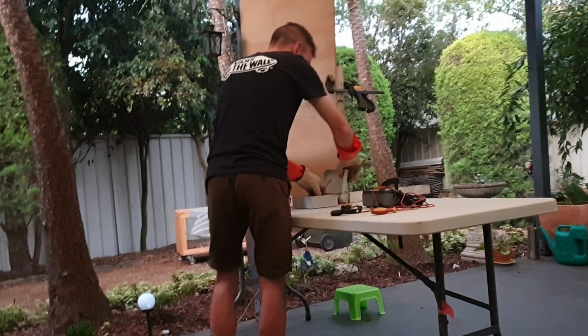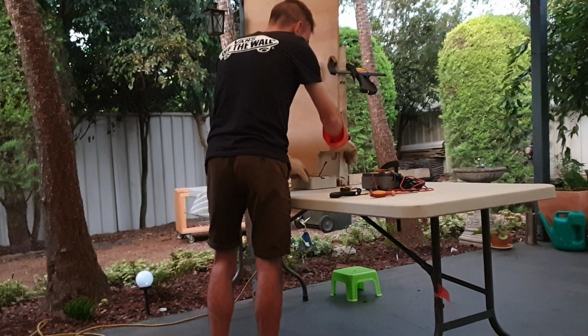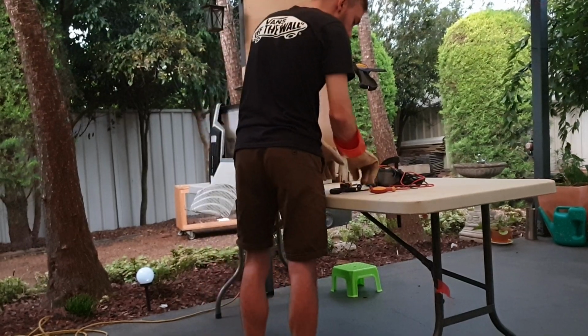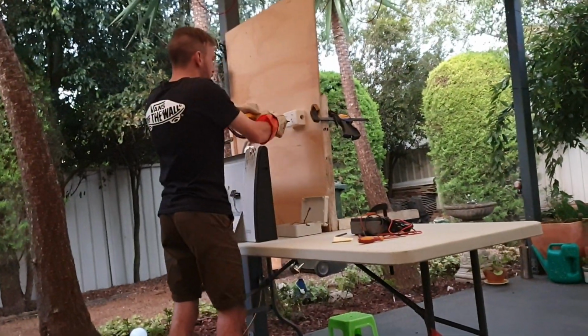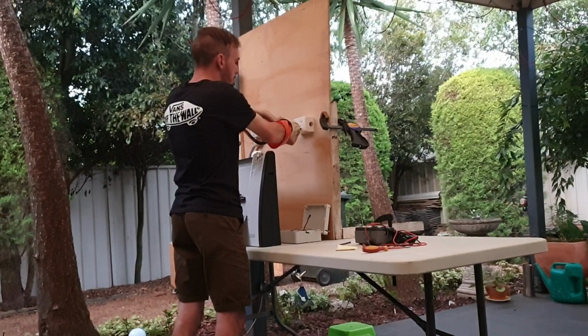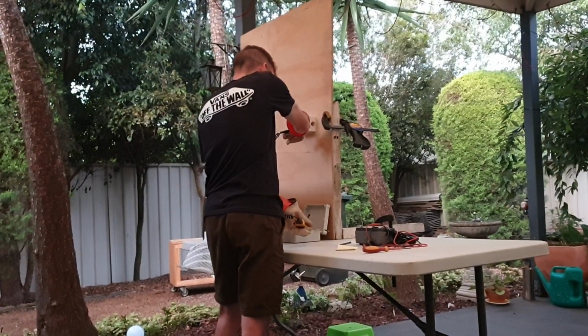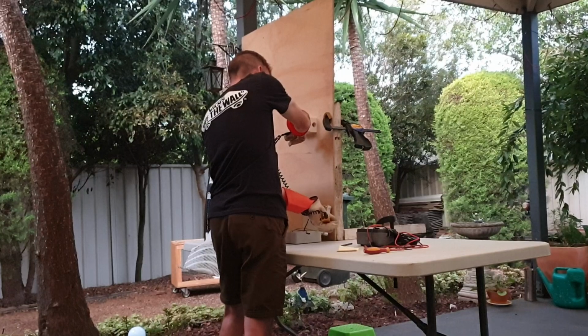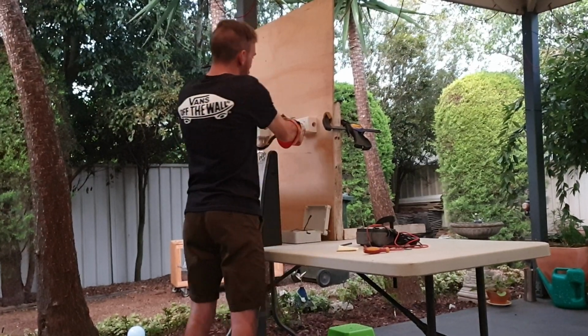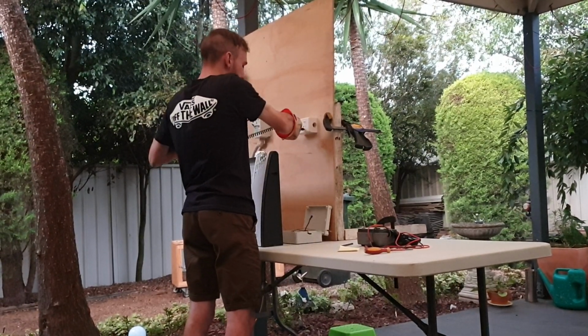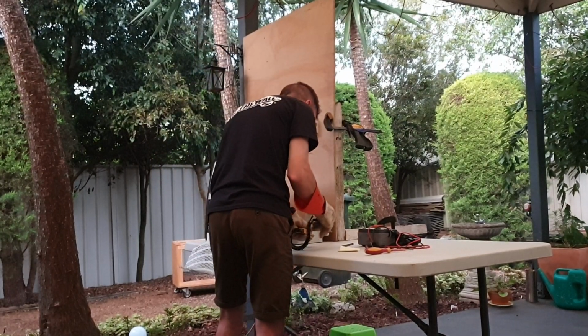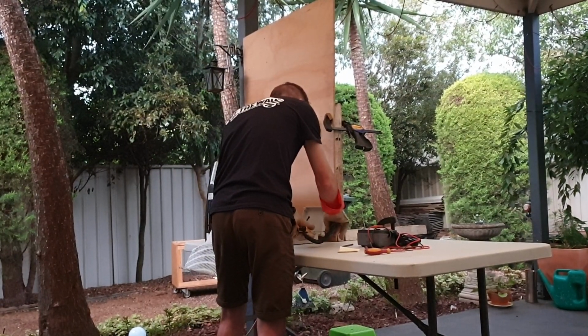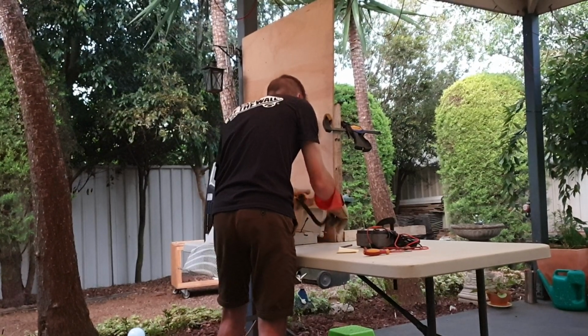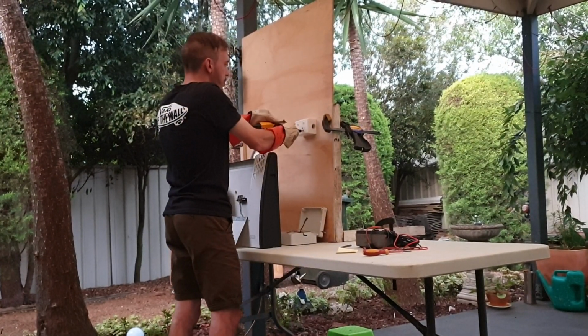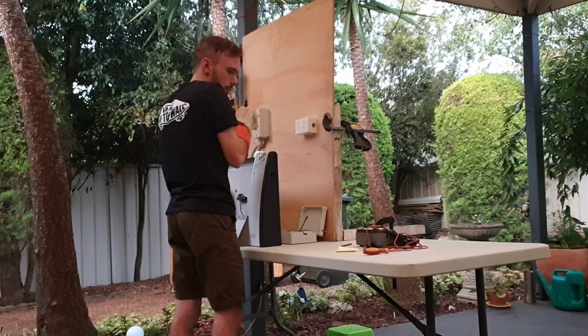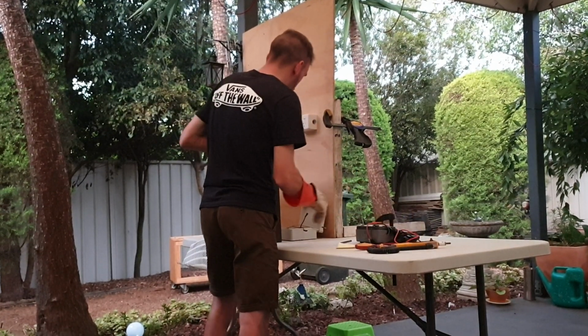Before we can move these cables or conductors out of the junction box, we have to test those, ensuring they're no longer live. Again, we're going to test the meter. Known live source voltage. We're going to test between the known source and the active, the neutral and the earth. There's no voltage. We're going to test the meter again. Now we're going to test between the conductors: active to neutral, active to earth, and neutral to earth. None of them have voltage. Test the meter one more time. That's correct. So now it's safe to handle the conductors from the junction box.